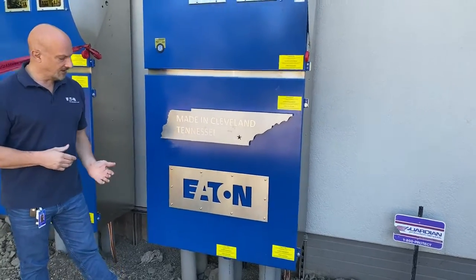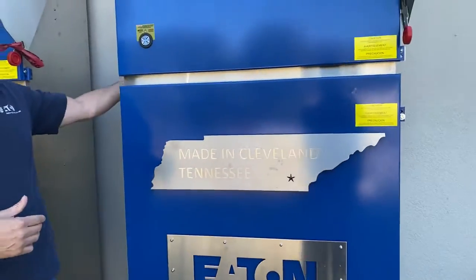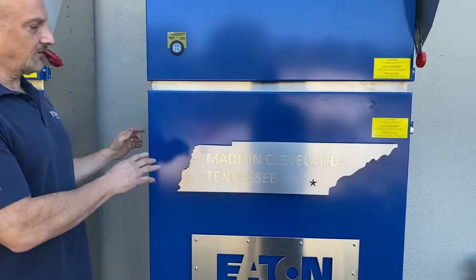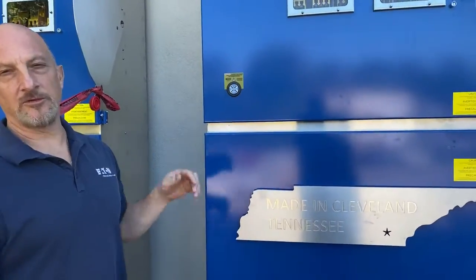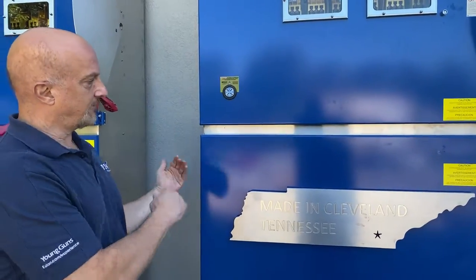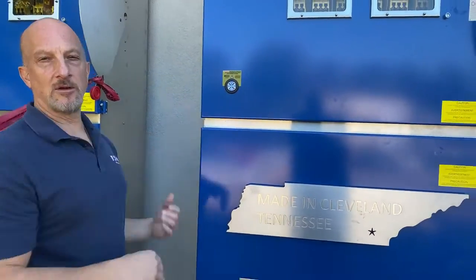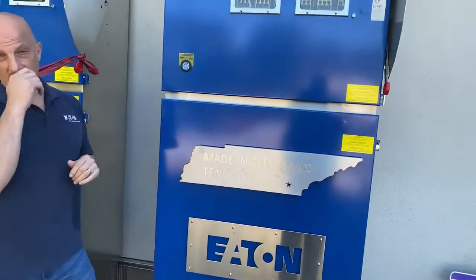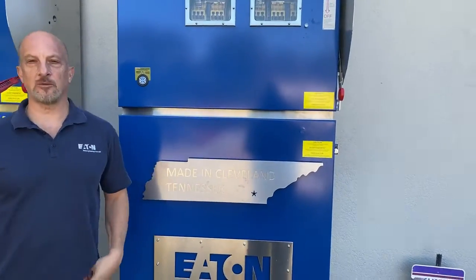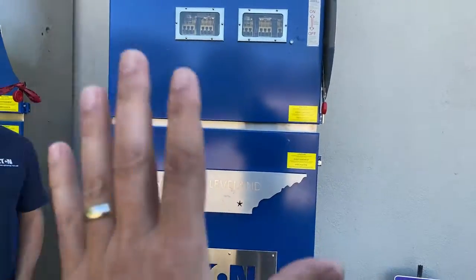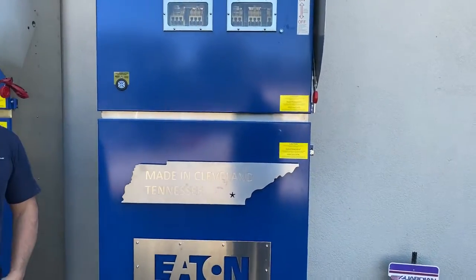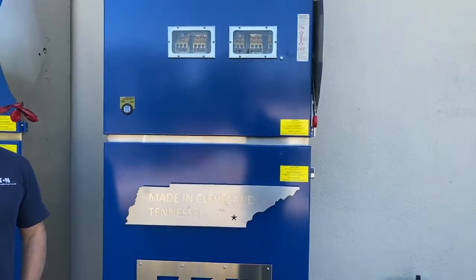Yeah, and by the way, the incoming wires go behind this barrier part here. So if we open up the doors, you can see on the inside there's actually barriers here and back here. So the wires go behind—for, okay, so your service conductors come behind a barrier into the top compartment. So that makes a lot of sense because I was noticing there's nothing up above showing those items.